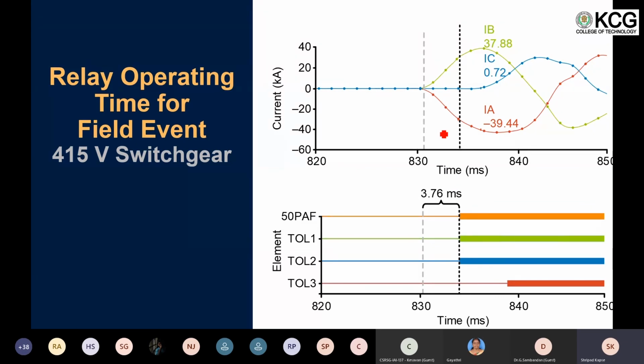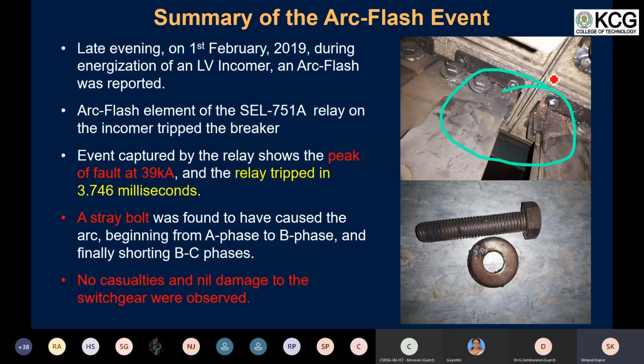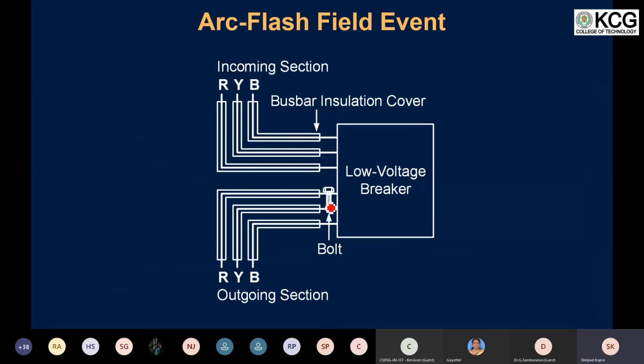Due to this fast operating time, the arc flash energy was significantly reduced, and the hazard to the people working close to the switchgear was mitigated or totally eliminated. The impact that this fault could cause on the primary equipment was also significantly reduced. As an overall restoration, the customer had to just replace some of the copper bars associated with the joints at the incoming level and at the outgoing level. There was no major damage to the primary equipment in this event.